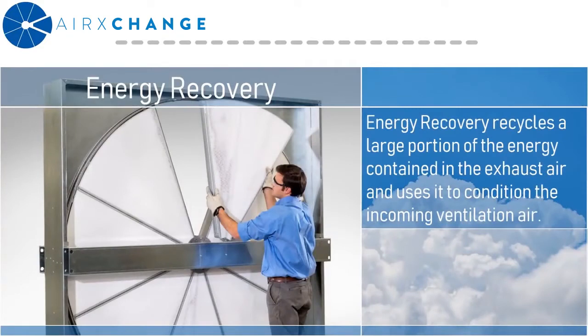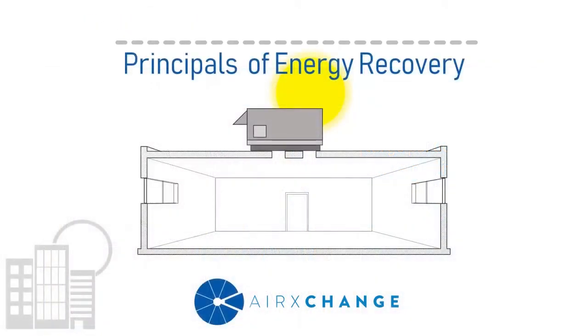So energy recovery in its basic form is merely an air-to-air heat exchanger. It's used to recycle a large portion of the energy in the exhaust air, and it uses it to condition the incoming ventilation air.